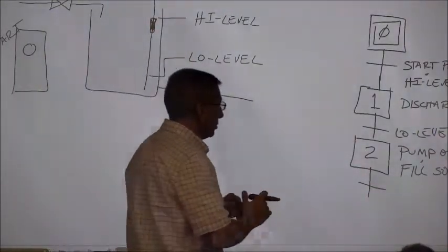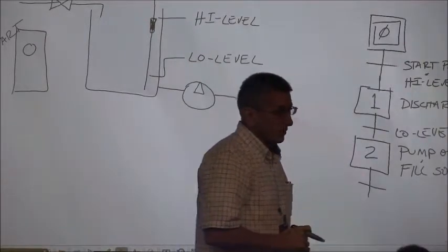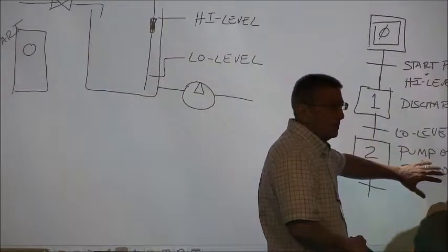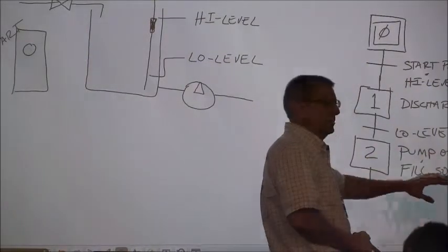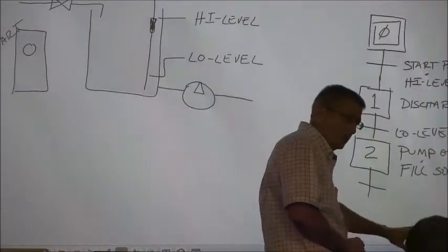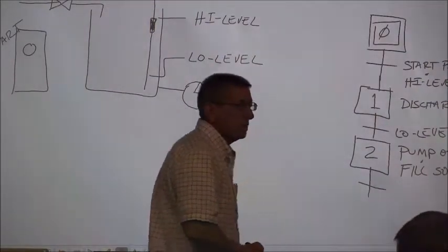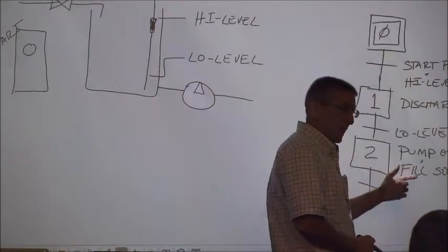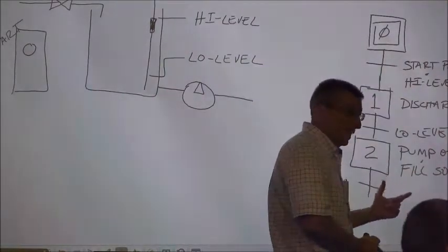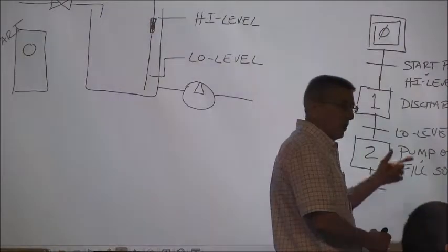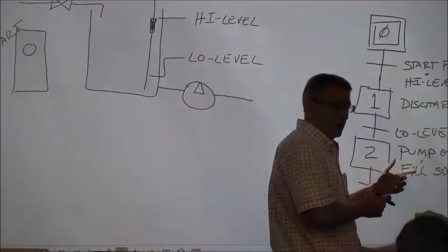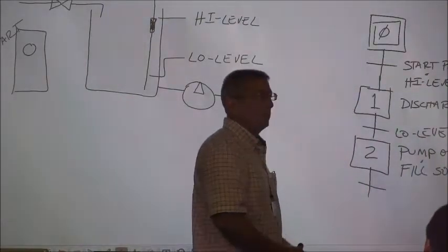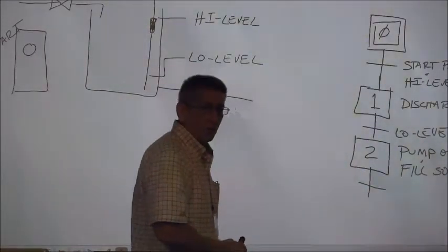You can put a lot of detail in this stuff too, can't you? Okay, we have pump off, and then we verify that the pump's off. As soon as we see the motor starter auxiliary contacts open up, that would be a transition. We do a pump off, shut the pump off, the auxiliary contacts open up. So, yep, pump's off, then we can turn on the solenoid.